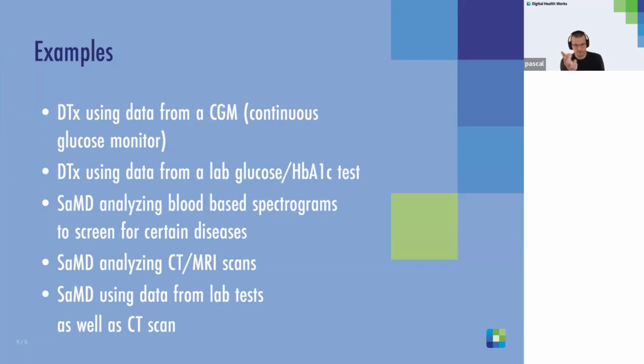Well, first, the main data comes from a CGM, so you would look at what regulation that falls under. Since a CGM is worn on the body, it is a normal medical device, so it's an MDR device. So the data comes from an MDR device, and this app would also be MDR.